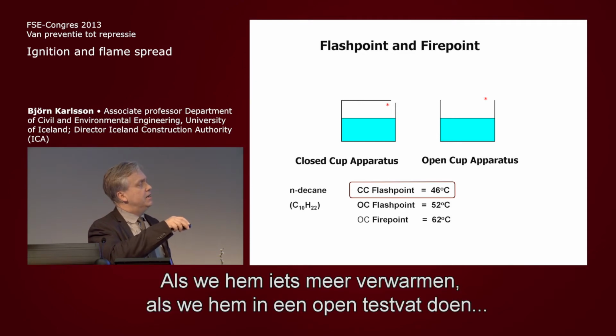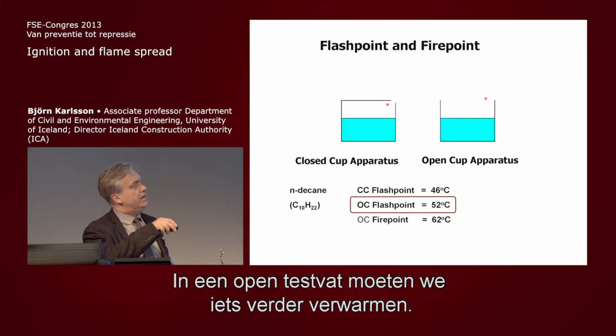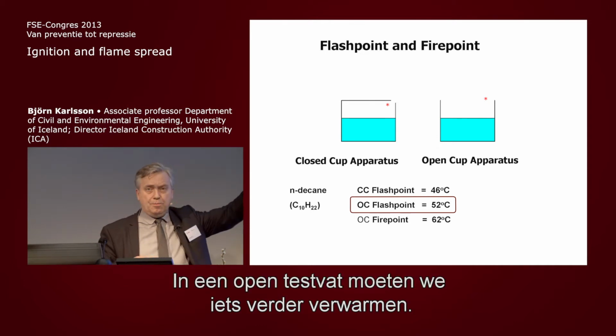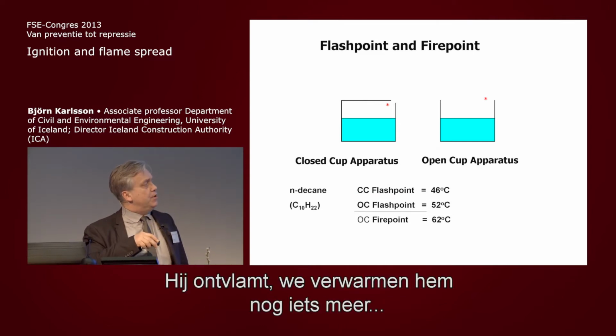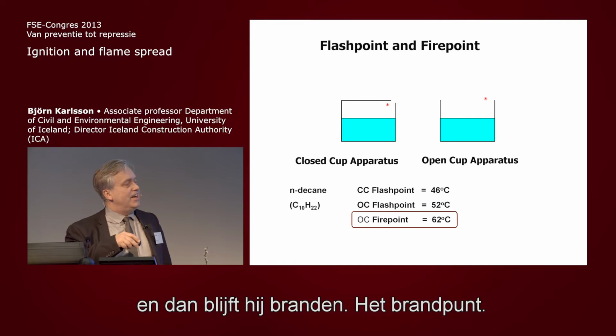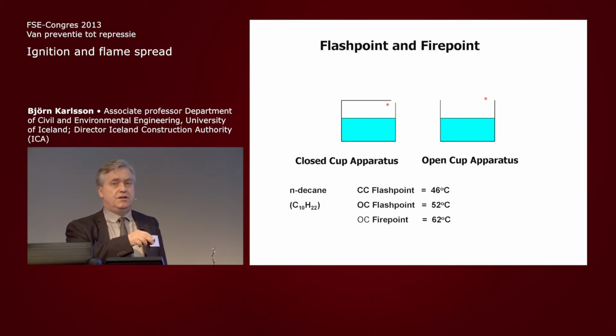If we put it in an open cup, we need to heat it a little bit more. It'll flash, and then we heat it just a bit more, and it will actually continue to burn with a sustained burning, at the fire point.